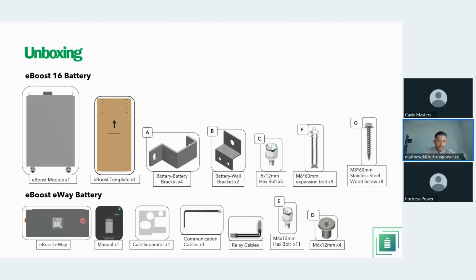Nuts and bolts, and then the eBoost E-way will include the E-way, the manual, and a cable separator that allows you to isolate your AC conductors and your DC conductors inside the chamber. Communication cables for battery to battery and battery to inverter, and then the relay cable, which allows the primary battery to signal to the other secondary batteries to turn on when everything is being commissioned. And then some nuts and bolts as well.